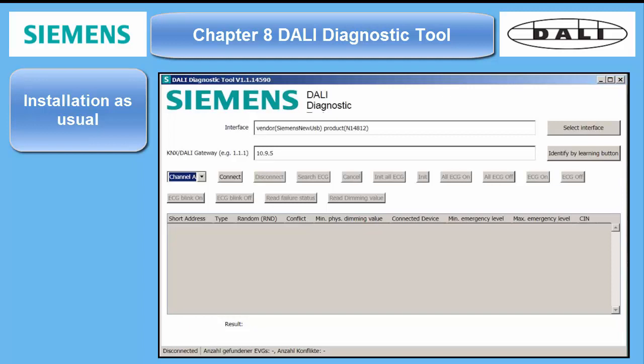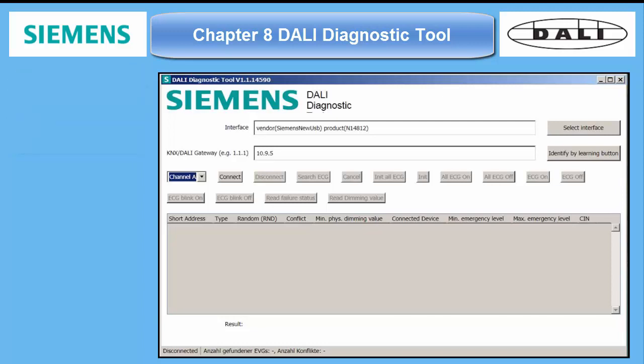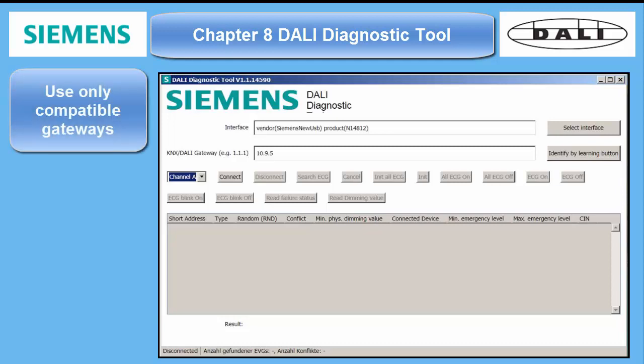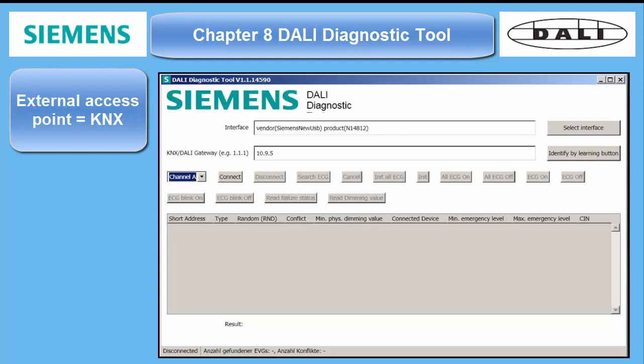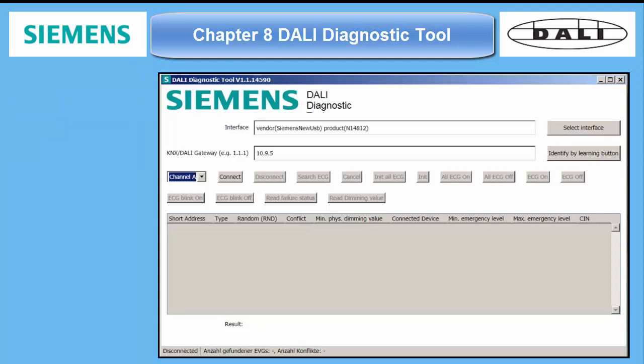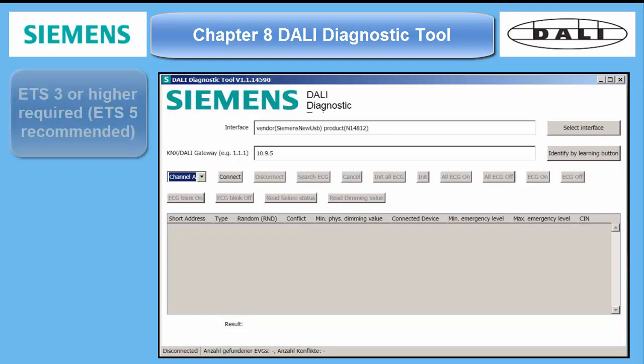The Siemens DALI diagnostic tool must be installed as usual. After installation you start it and see the main page. The communication with the DALI bus always requires one of the previously mentioned compatible gateways. Since these gateways only have two access interfaces — KNX and DALI — the external access point is KNX. Actually all available KNX bus interfaces can be used. Make sure you are also running ETS 3 or higher on your PC because of the interface driver called Falcon.